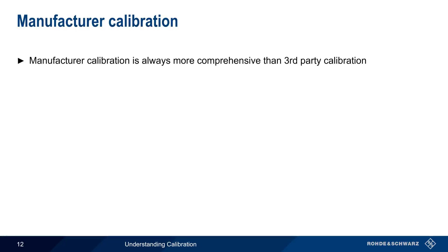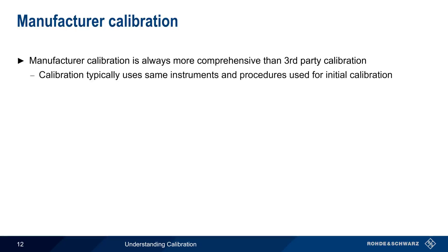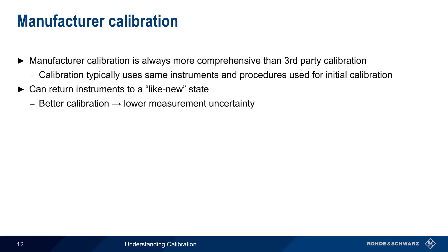Compared to third-party calibration, manufacturer calibration is always more comprehensive and often uses the same instruments and procedures that were used for the instrument's initial calibration during production. Because of this, a manufacturer calibration can return instruments to a factory or like-new condition. This higher-quality calibration also provides lower measurement uncertainty and all of the benefits associated with lower uncertainty.